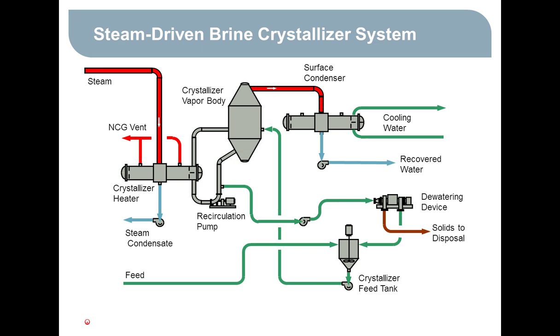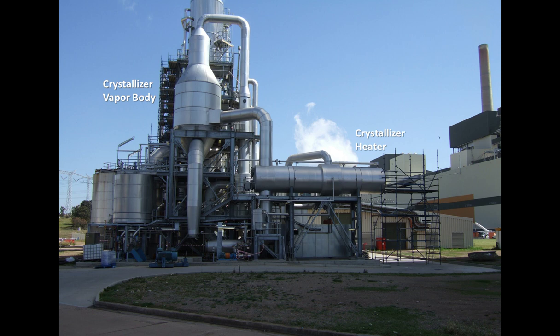This is a picture of a forced circulation crystallizer. Again, the main thing to note is that the heater is sitting well below the level of the liquid that sits up in that crystallizer tank, so that the heat exchanger is flooded and no boiling occurs and no crystal growth occurs in that heater. It all goes on in the vapor body.